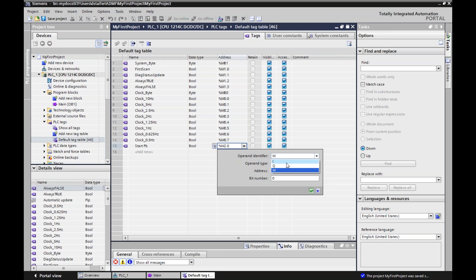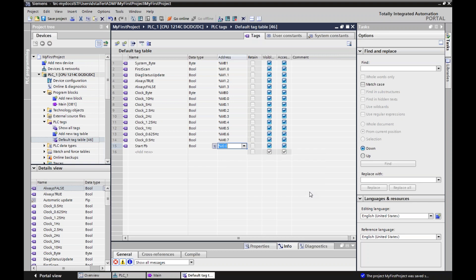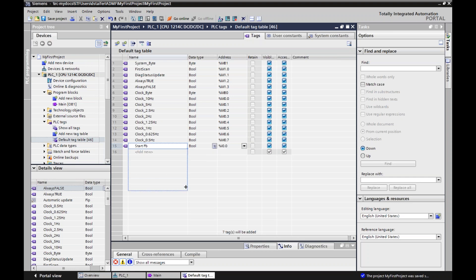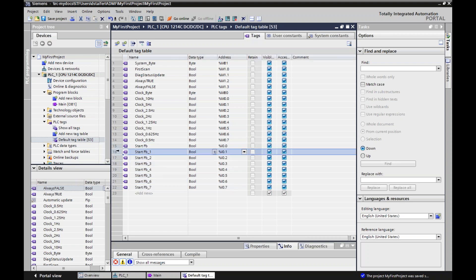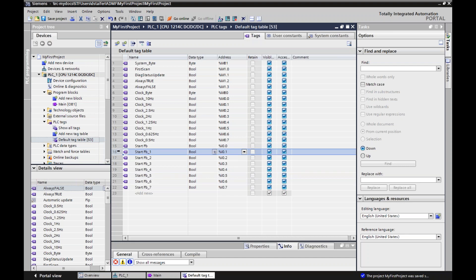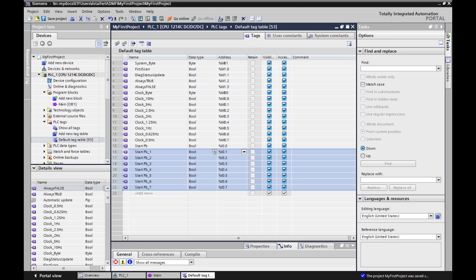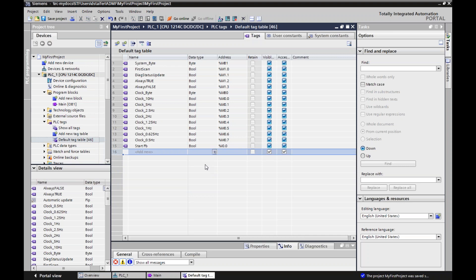So a memory bit will be just something that turns on and off inside the controller. An input is physically linked to an input on the PLC. An output is physically linked to an output on the PLC. So I can do input, do my start address, so I'll say 0, bit number 0. Hit the green check mark, and now it's there. Let's say all of these are start and push buttons in some capacity. Like Excel, if I move my cursor over the square and it becomes a plus sign, I can copy and paste and check this out. It auto-numbers and it auto-continues, just like Excel.